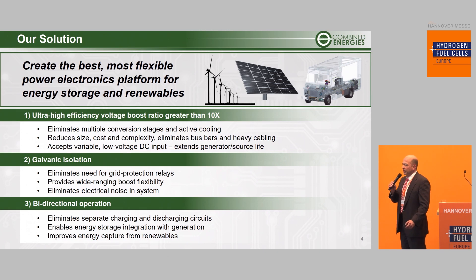It also needed to have galvanic isolation. When we are grid-connected, we obviously had to have that, but also more people we talked to really appreciate the fact that galvanic isolation eliminates noise back and forth between and among the systems. The third attribute is bi-directional operation, so we can boost power in one direction and buck power back in the other direction. For example, working with ultra-capacitors, flow batteries, or energy storage, we can charge and discharge — not simultaneously, but with the same system.